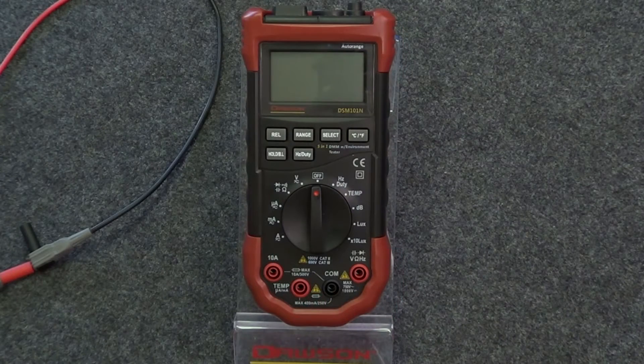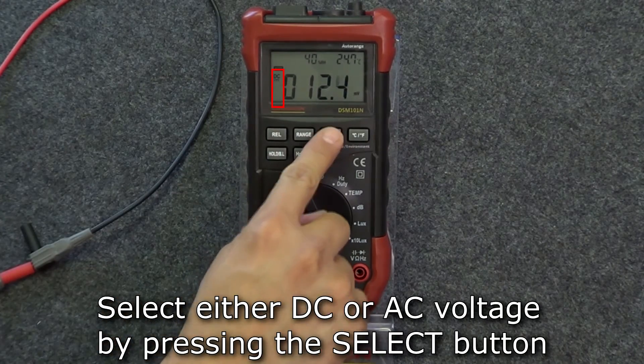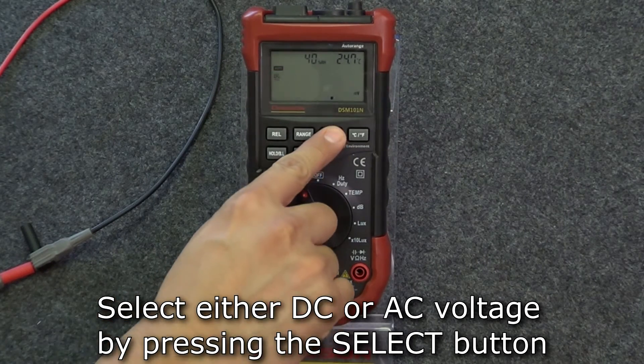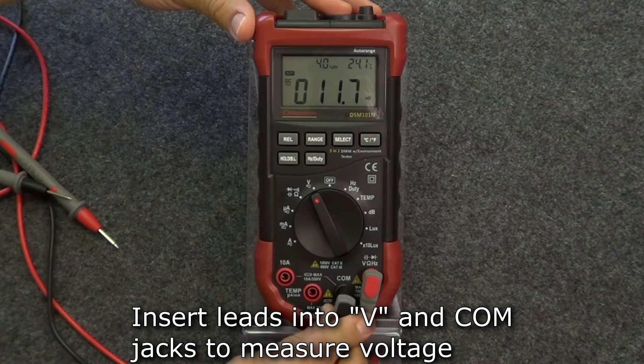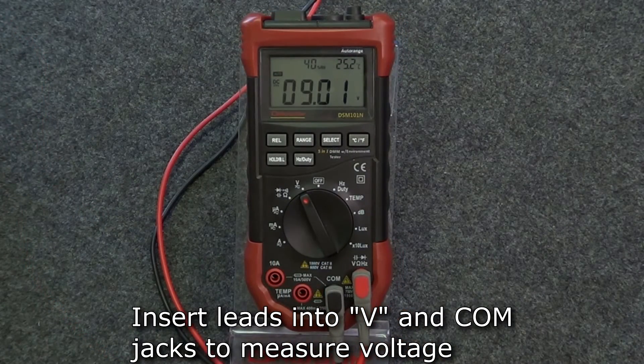Let's start with the electrical measurements. To measure voltage, move the rotary switch to the voltage position. The default mode is DC voltage. If you need to switch to AC voltage, press the select button and the meter will switch to AC voltage. To switch back to DC voltage, press select again. Insert the red test lead into the voltage jack and the black lead into the COM jack, and the meter is ready to measure voltage.